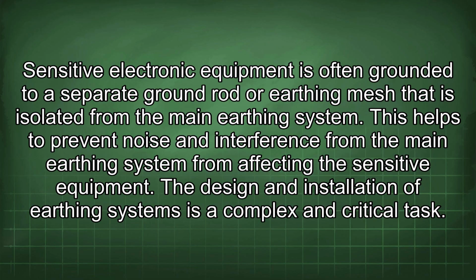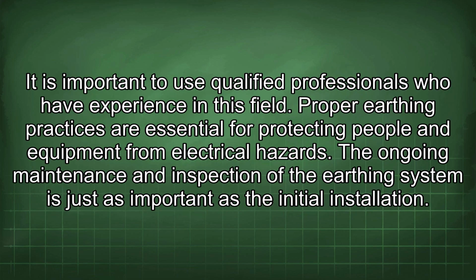Sensitive electronic equipment is often grounded to a separate ground rod or earthing mesh that is isolated from the main earthing system. This helps to prevent noise and interference from the main earthing system from affecting the sensitive equipment. The design and installation of earthing systems is a complex and critical task. It is important to use qualified professionals who have experience in this field. Proper earthing practices are essential for protecting people and equipment from electrical hazards.